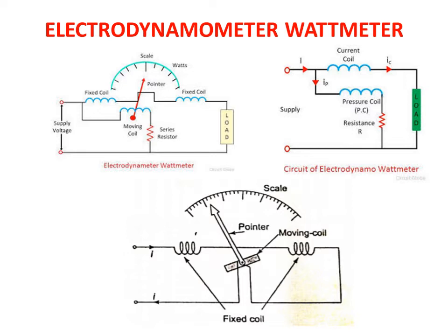Okay, so this electrodynamometer type instrument is a transfer instrument which is calibrated with a DC source and, without any modifications, the same instrument can be used for AC measurement also with the same accuracy. Therefore, this type of instrument is often used in AC voltmeters and ammeters with high accuracy with small modifications. So this electrodynamometer type instrument is used for both AC and DC quantities.